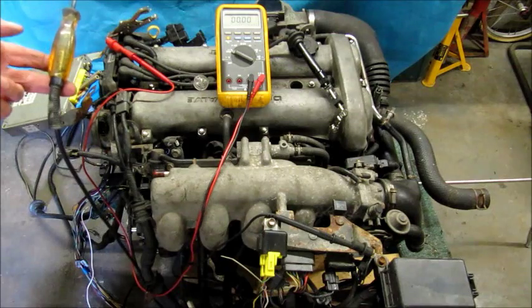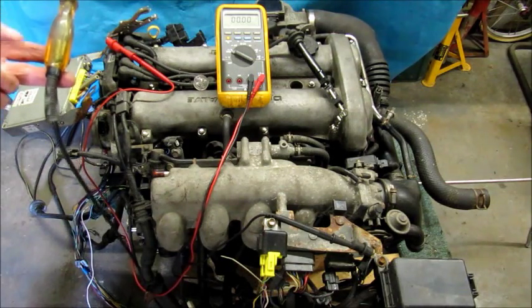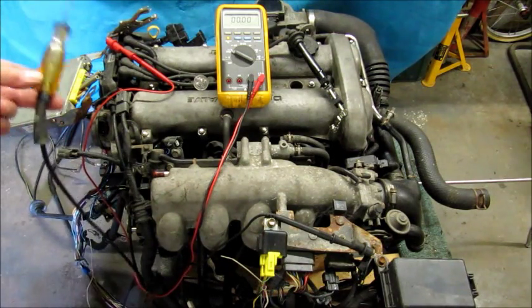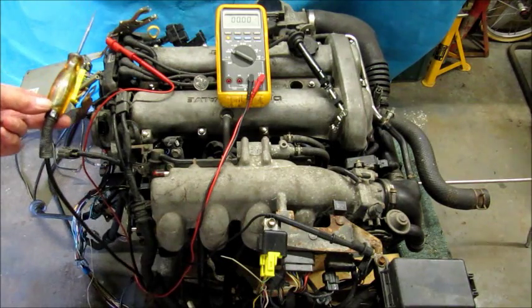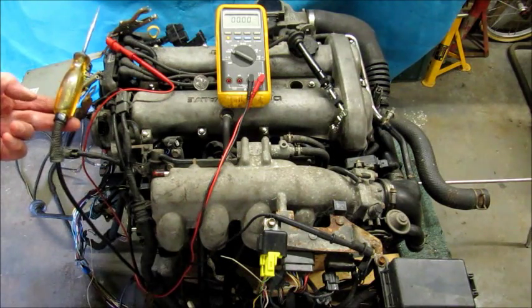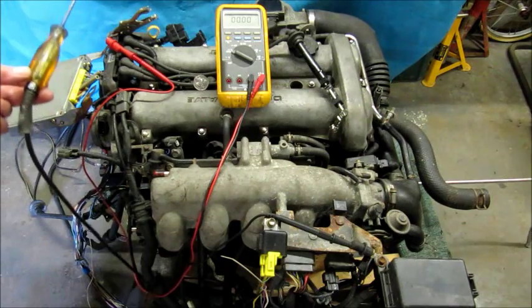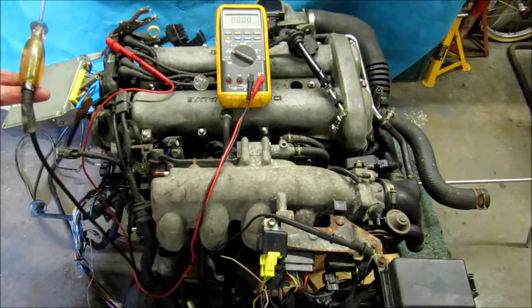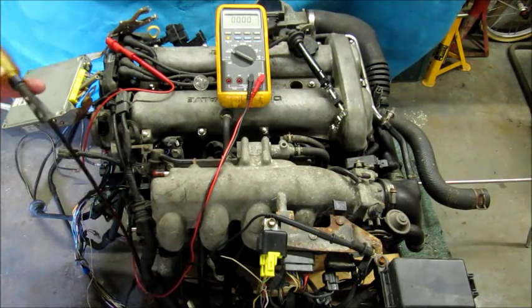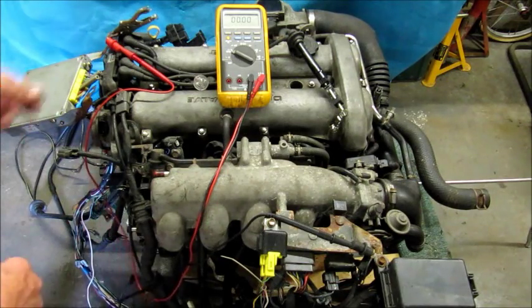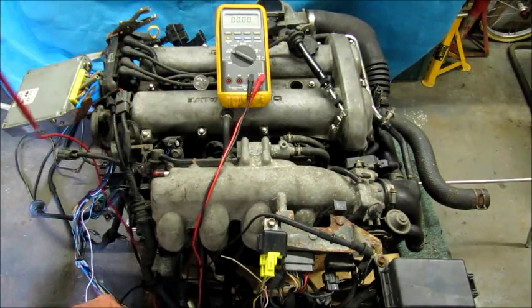You have to be careful with this type of tester. It's considered a low impedance tester. It actually puts a load on the circuit, which is useful when you're checking power circuits. However, it can be damaging if you use it on electronic circuits. The reason I like it for power circuits is if you use the DVOM, you can get some misleading readings.